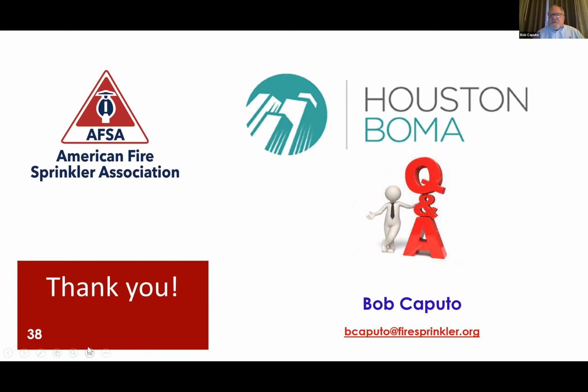And by the way, the standard for inspection, testing, and maintenance of all of the water-based systems, that includes your fire pump, your fire sprinkler system, standpipe systems, all of that is covered in NFPA 25. And unfortunately, if that hydraulic data nameplate, if that placard is missing, that is a deficiency in your annual inspection. And someone is going to have to find the original drawings if they're available, or you're going to end up paying someone to come out and survey the system and recalculate and recreate that card to be in compliance with NFPA 25, which is the standard for inspection, testing, and maintenance. That is a great question, by the way.